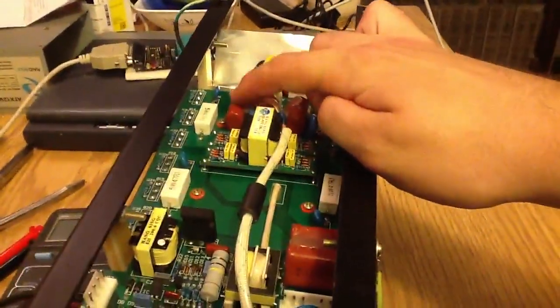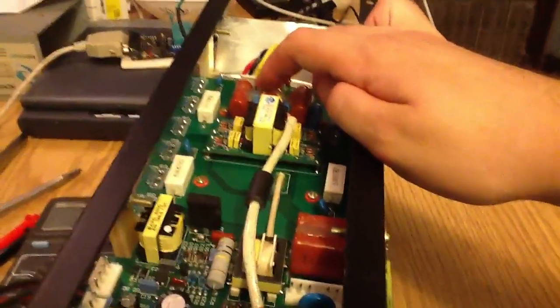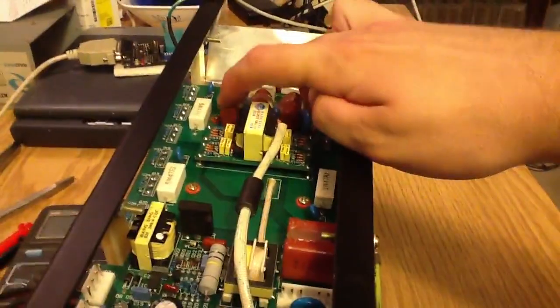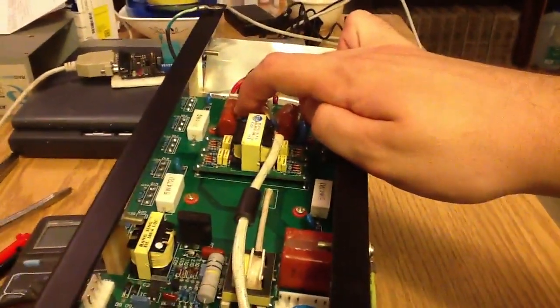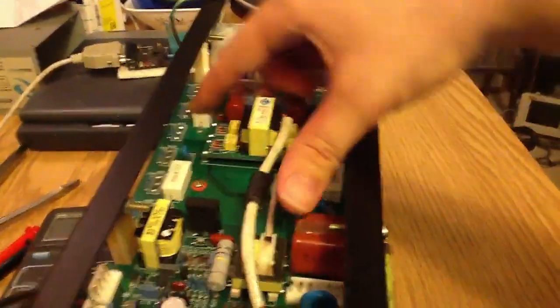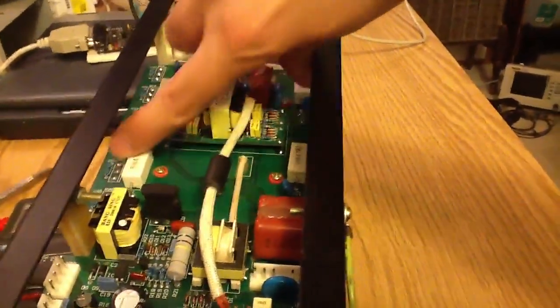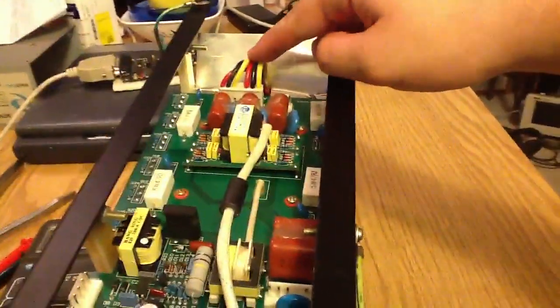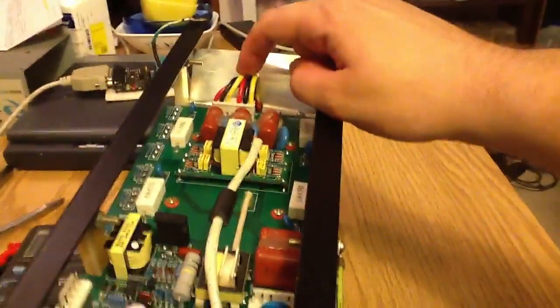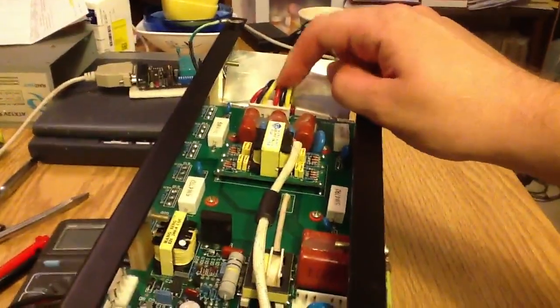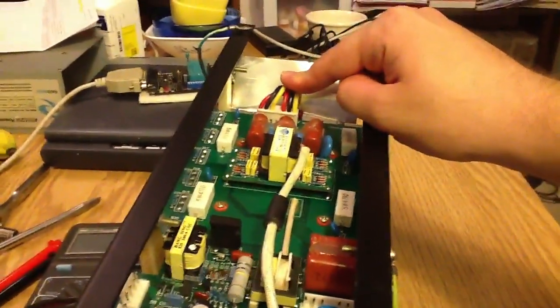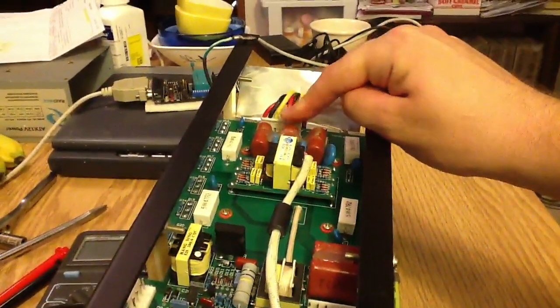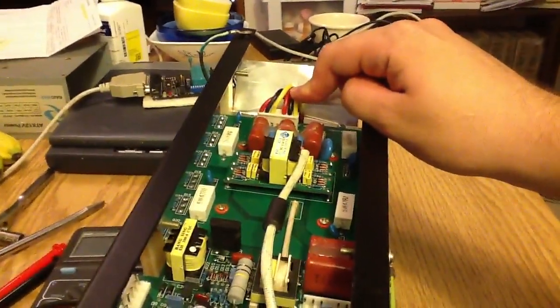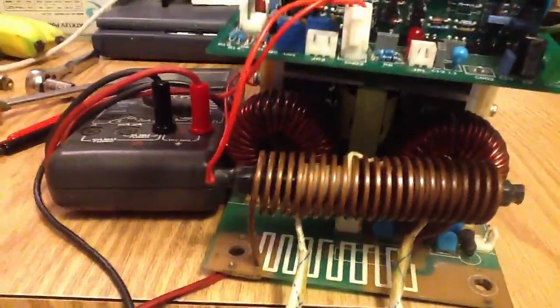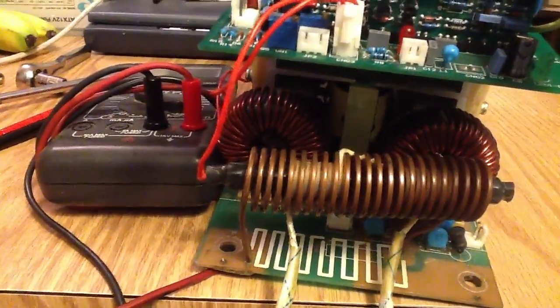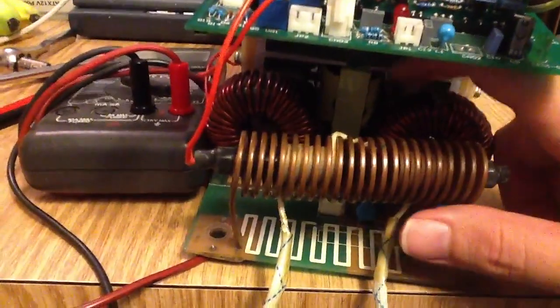Depending on how this is laid out, this may even be an essential thing to have in this circuit, since there's always going to be a DC component to your switching, and this would block that. You don't want DC getting into the coil of your transformer for a number of reasons - first, it could burn it out just from too much current, and also it could cause saturation of the transformer core, and that's bad. That'll cause too much current to flow and burn out your transformer.